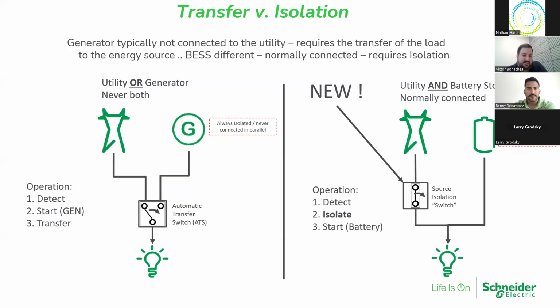If you look at the diagram on the left, the transfer switch, if you imagine the places you can place an inverter on here and why the transfer switch won't work, and this will help when we go through a one line in a few slides. If you replace the generator here with an inverter, well, that's not great, right? Because 90% of the time you do want to be connected to utility, in which case your inverter and your BESS system are completely out of the picture.